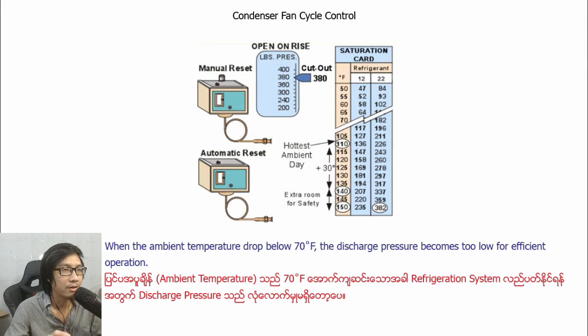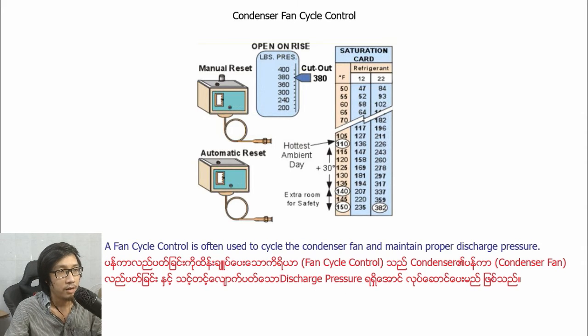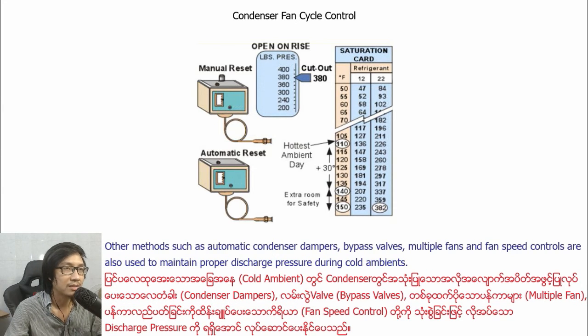Condenser fan cycle control. When the ambient temperature drops below 70 degrees Fahrenheit, the discharge pressure becomes too low for efficient operation. A fan cycle control is often used to cycle the condenser fan and maintain proper discharge pressure. Other methods such as automatic condenser dampers, bypass, multi-fan operation and fan speed control are also used to maintain proper discharge pressure during cold ambient.